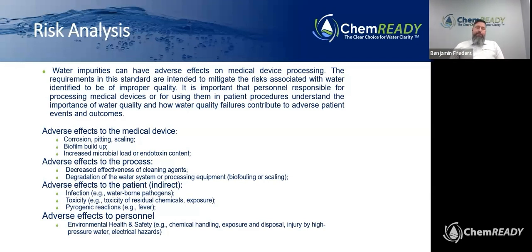It can also have adverse effects to the process, so decreased effectiveness of cleaning agents, degradation of the water system itself or the processing from biofouling or scaling. And then effects to patient and personnel could be infection, toxicity, fevers, and environmental health and safety from chemical handling, exposure, and injury, worst case scenario. So risk analysis must be performed by each facility per the standard to identify each of these hazards, how they can have effect on your particular facility's system.